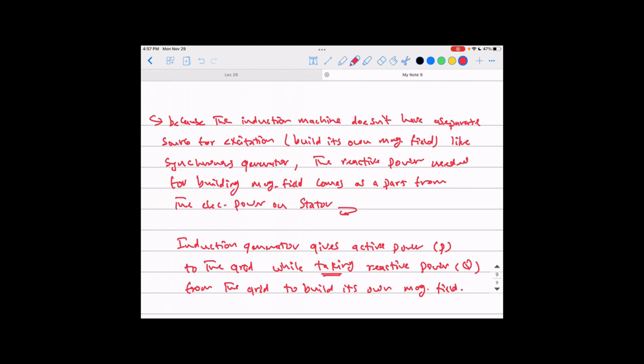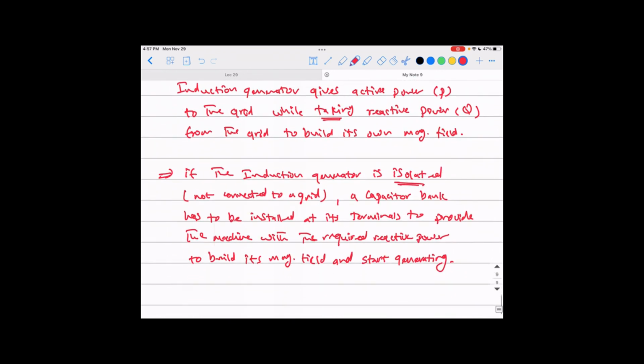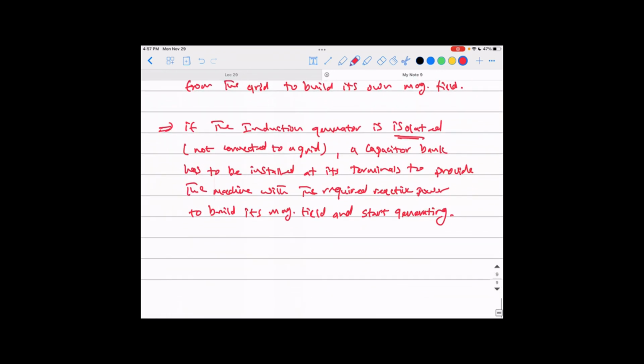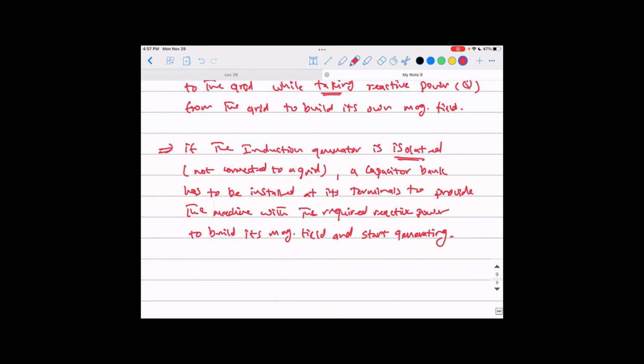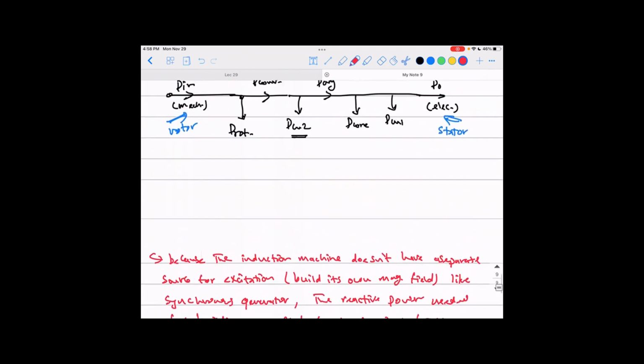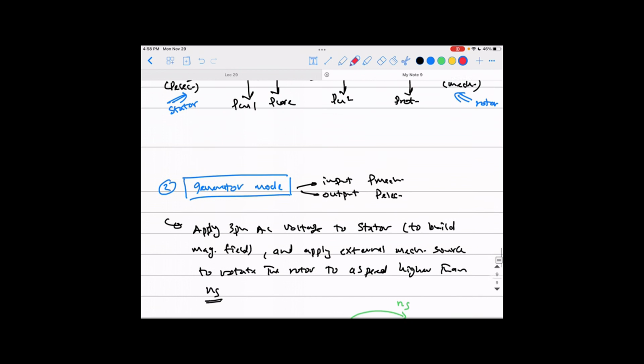And that's why the induction machine can just take Q from the grid. It does not have the ability to generate reactive power and give it to the grid, and it's just a very basic mode like that. Like we said, if you're not connected to the grid, like you have an isolated load or something, then you don't have any source to get reactive power from. So you have to install capacitors, because capacitors give reactive power. So the capacitors installed on the machine's terminals can give it the reactive power needed to build its own magnetic field and start generation. Okay, guys? So that's how the induction machine works as a generator. So that's the second mode of operation.